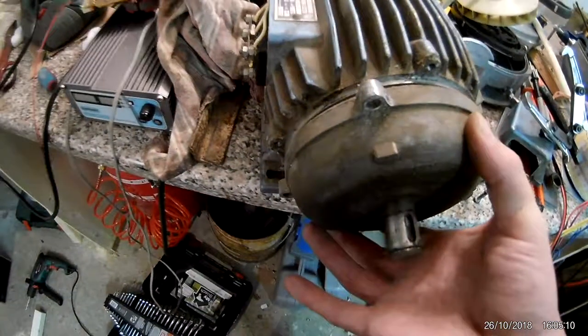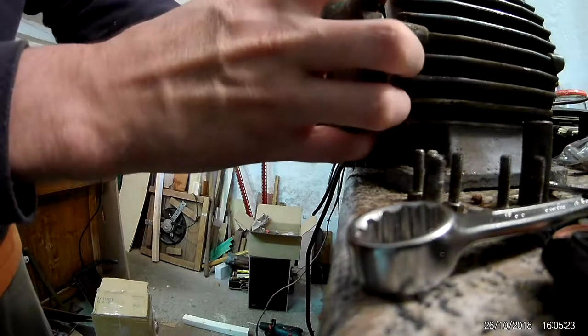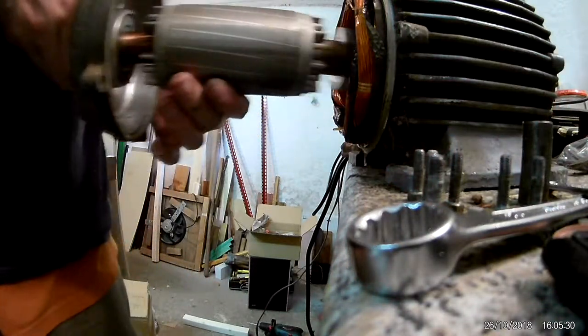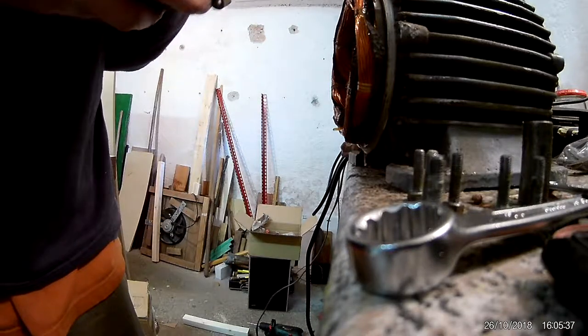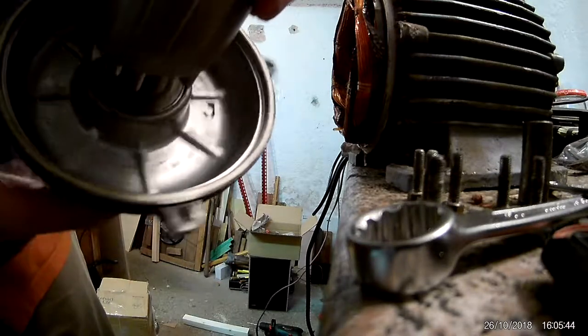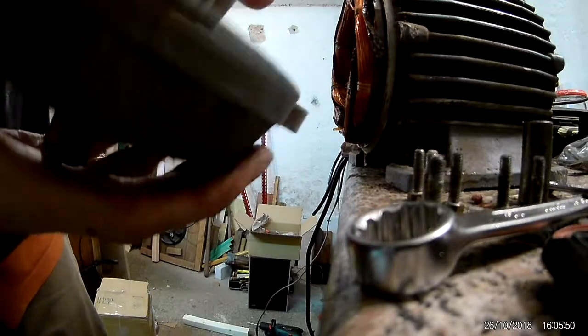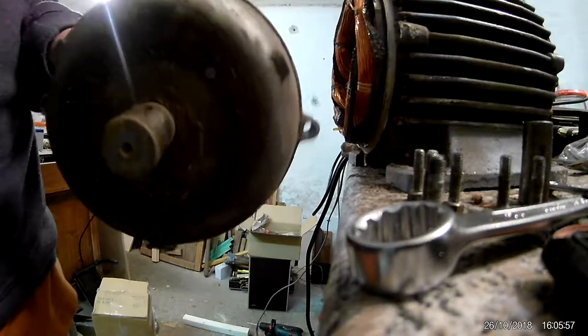This is apparently the other bearing that has the strange noise. That bearing is even more shot than the one on the front. I need two hands for that — I'm just going to slide out the rotor. There we go. The back bearing is still seated in there and it is quite loose.